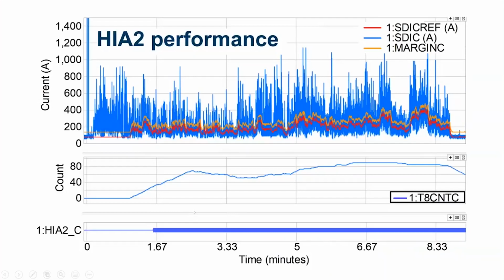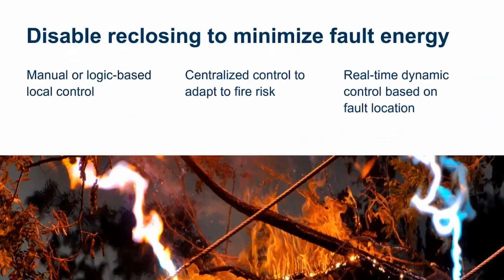This is from an actual field event, and we saw that although the 50 and 51 elements did not pick up, the tripping bit and the alarming bit both picked up for this arcing fault. So we have talked about events that we get from a high impedance fault or from the ArcSense technology algorithm. Next, I'm going to talk about reclosing, or why you would want to disable reclosing. Generally, electrical utilities use automatic reclosing to improve service reliability so that you don't have longer outages for momentary faults. But it might be desirable to block or disable reclosing in some cases where you have high fire danger areas or any areas where wildfire could be a common occurrence.